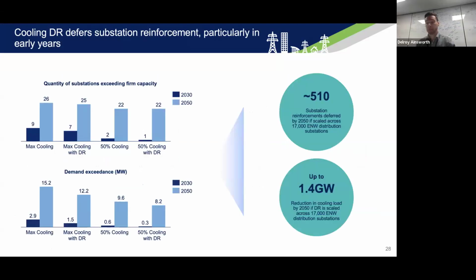Dal? Yeah, I'll pick this one up. So, excuse me. Yeah, so we took the demand figures from the UCLC model and then added them to our baseline forecasts. So that's the forecasted uptake of EV and heat pumps from our DFES, and then the AC from the UCLC modelling. We then extrapolated across two full primary substations to better understand the potential impact of cooling on the network, identifying the need for reinforcement with and without DR. Those two primary substations consisted of 36 distribution substations, so the numbers you can see on the graphs are out of a total of 36.